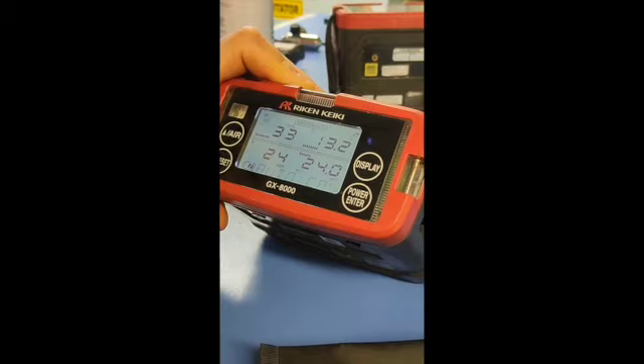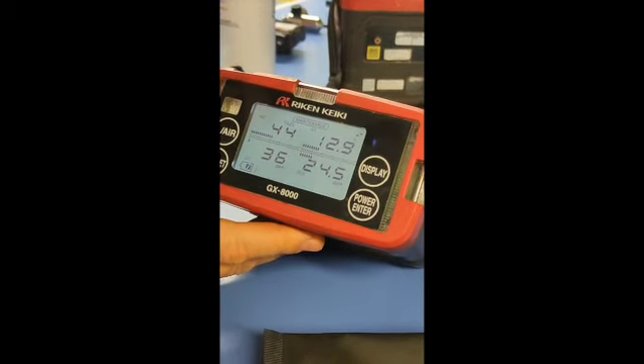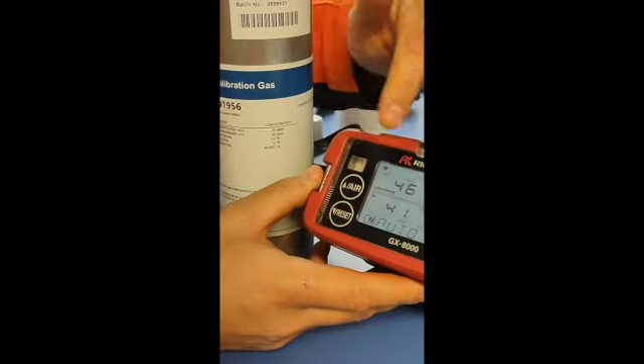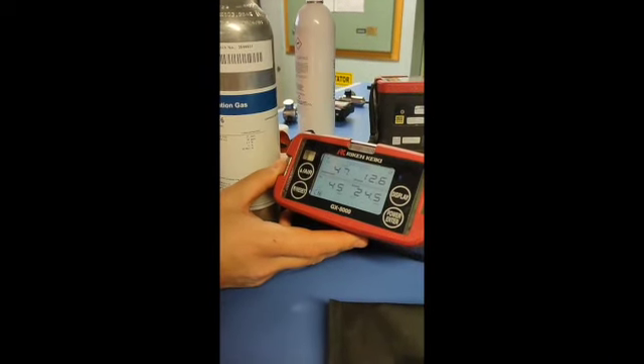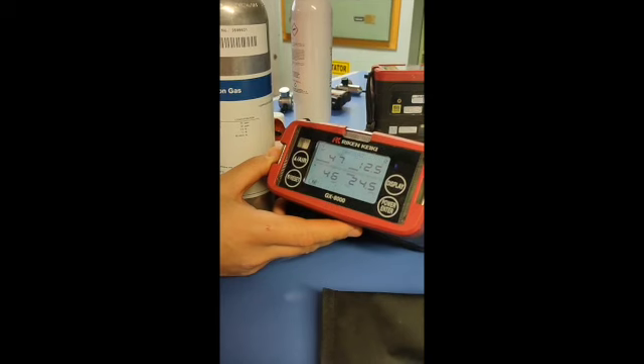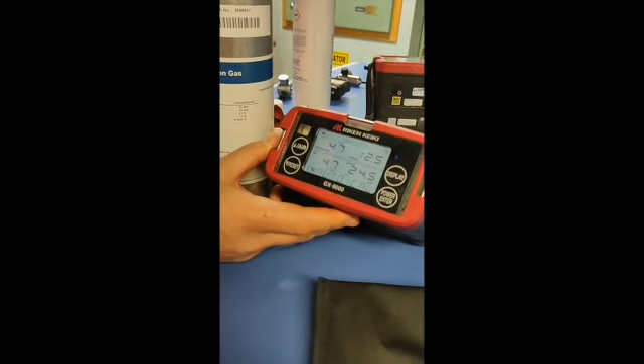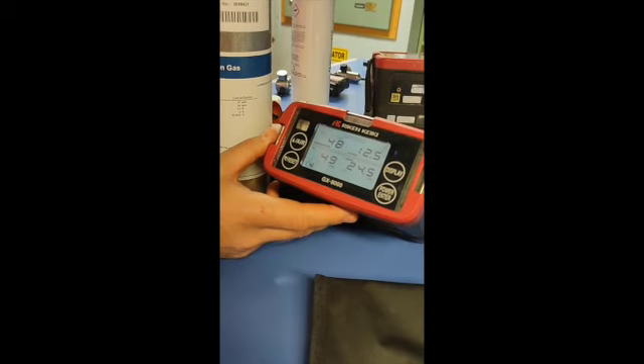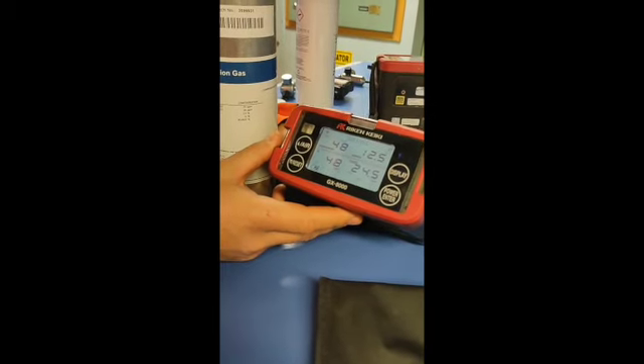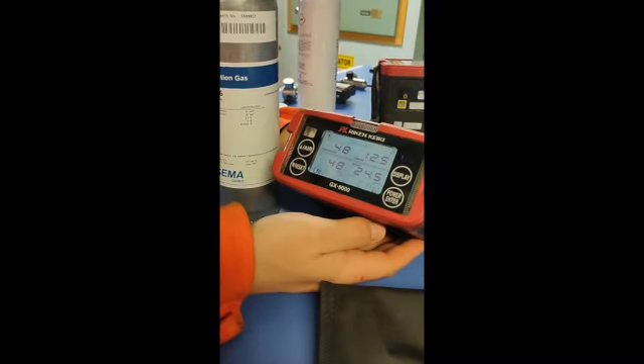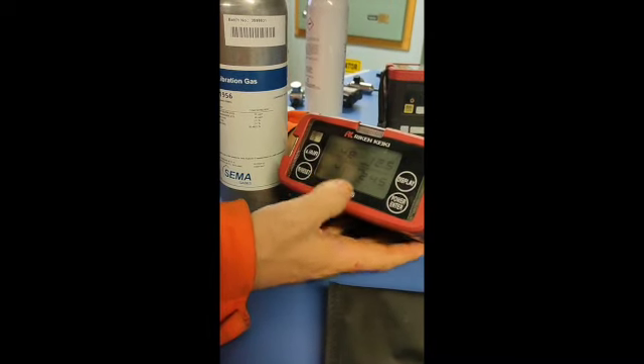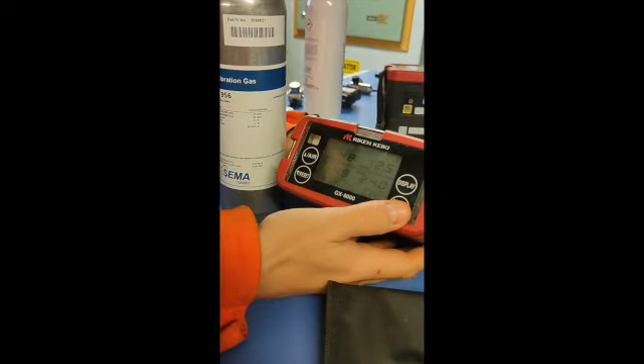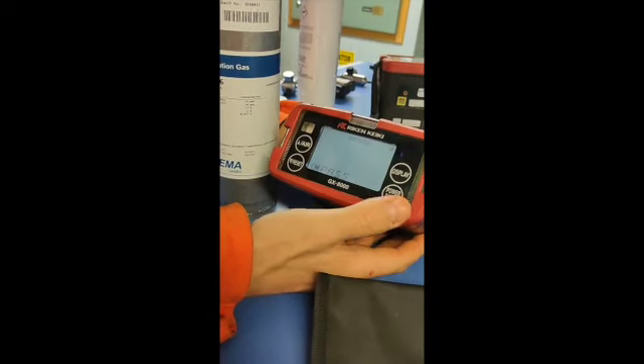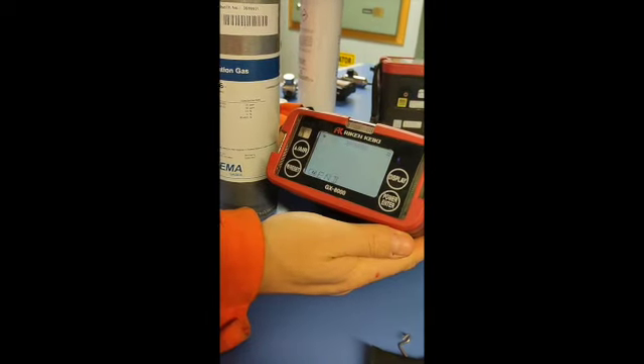We are in auto cal mode and we are waiting for the same values of the bottle to appear on my portable gas detector. Whenever these values are stabilized, the maker says around 1 minute. It can be faster than 1 minute, it can be 30 seconds. You have to press enter, and then the word pass will be displayed. So I will press now, it's already stabilized. Pass. So this is auto cal.